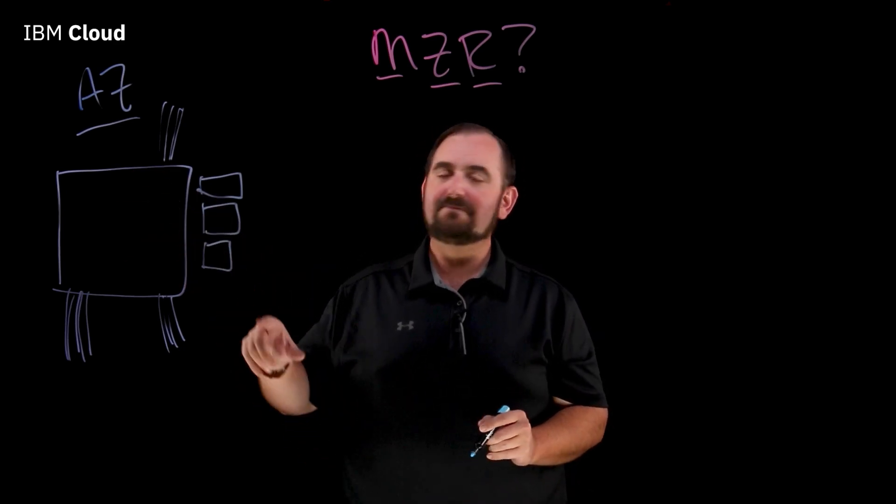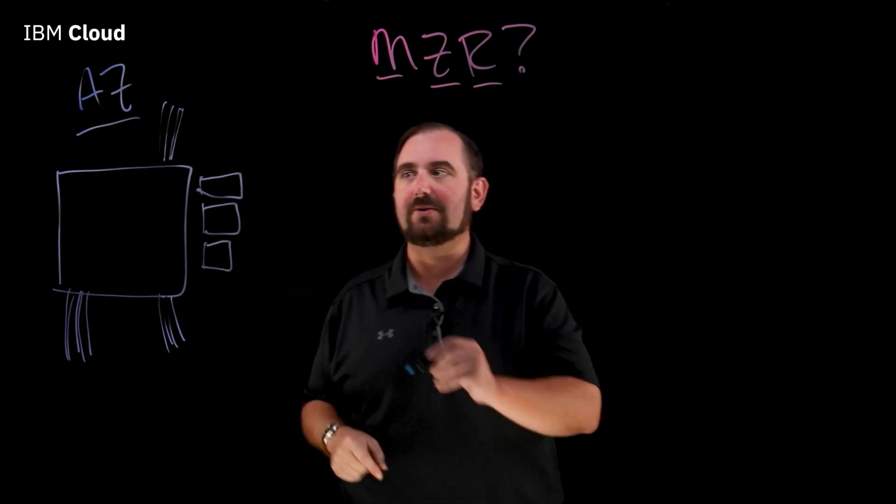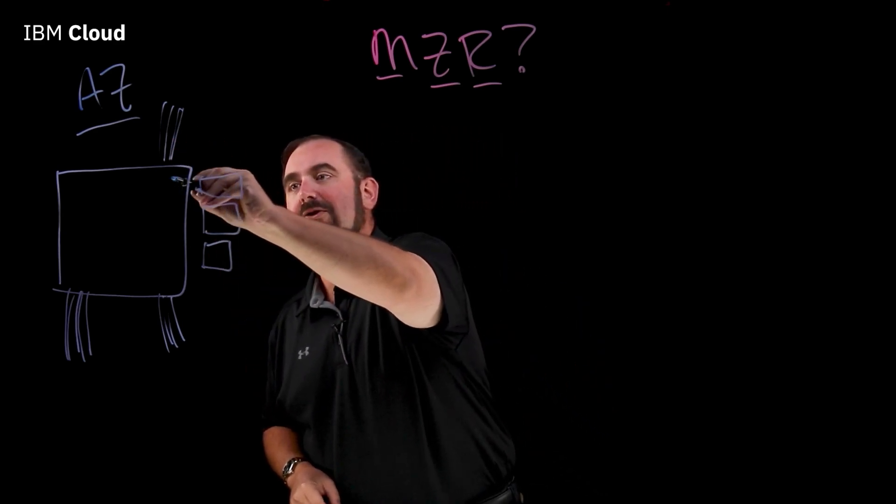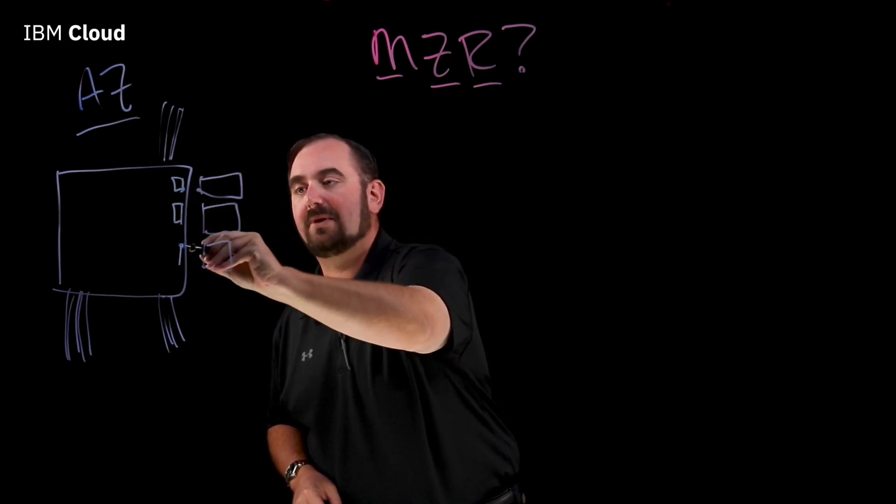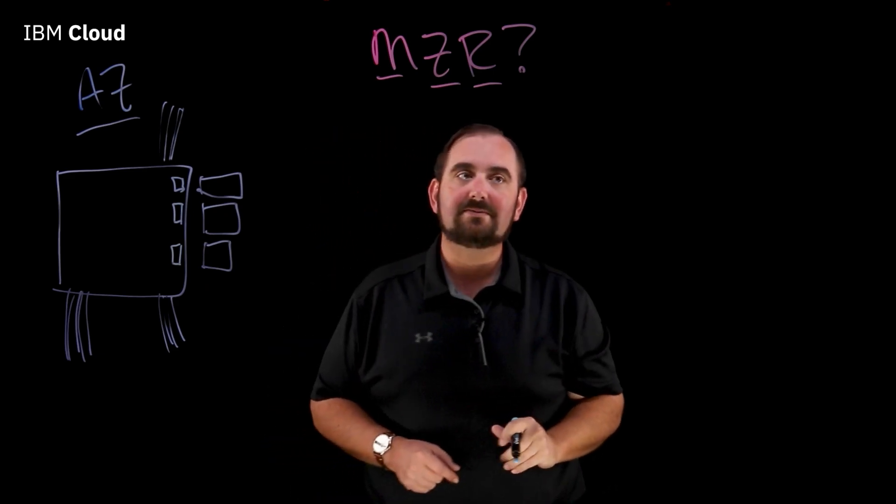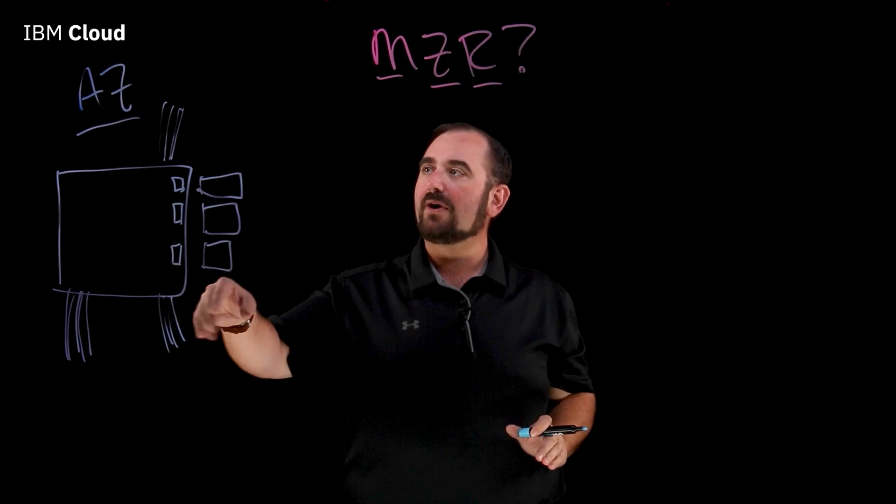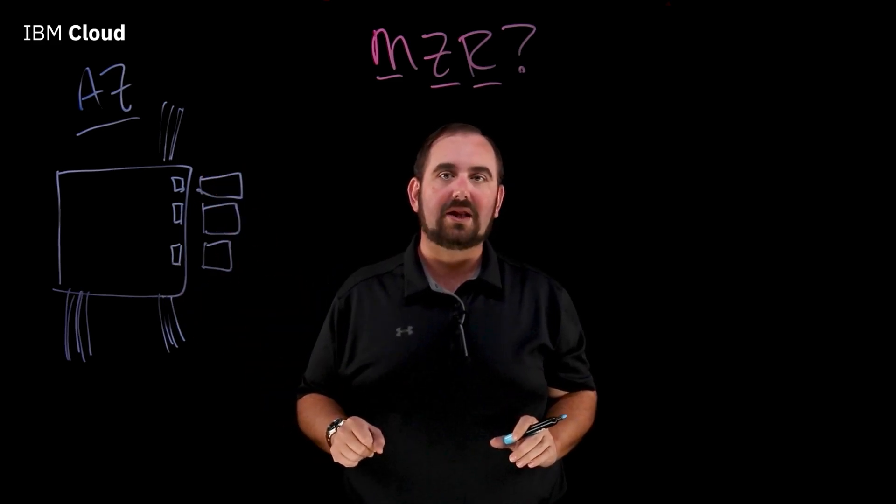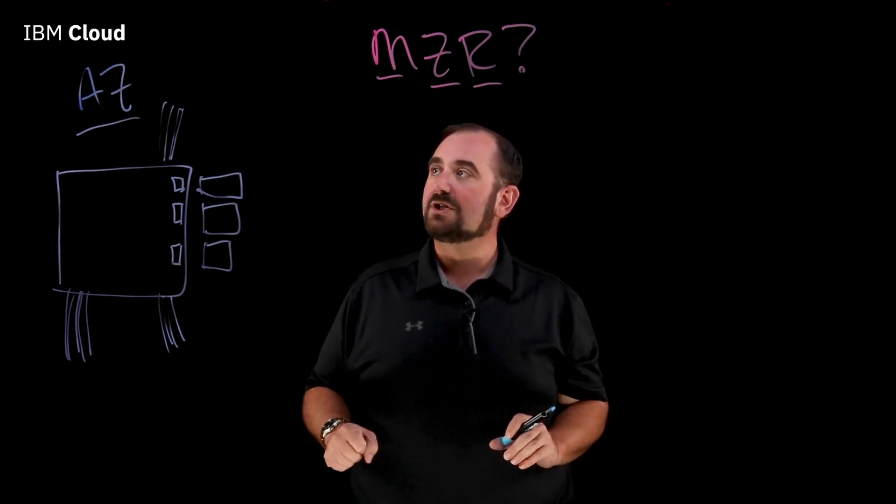And in addition to those generators, in order to bridge the gap between when the power goes off and the generators go on, we have huge UPS systems. UPS is an uninterruptible power supply. And those UPS systems are sized to get us 15 to 20 minutes between when the power comes off and the generators come all the way online. Now, in practice, we don't need anywhere near that much time, but it's just a good thing to have.